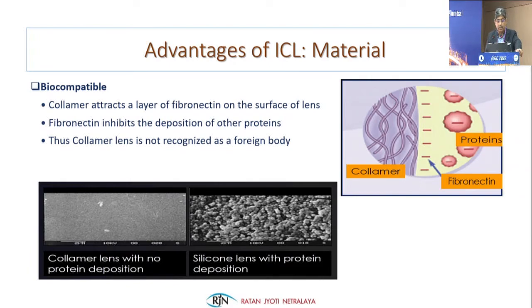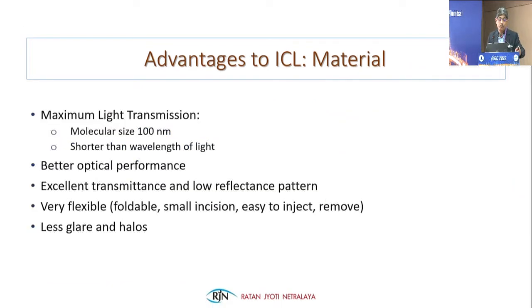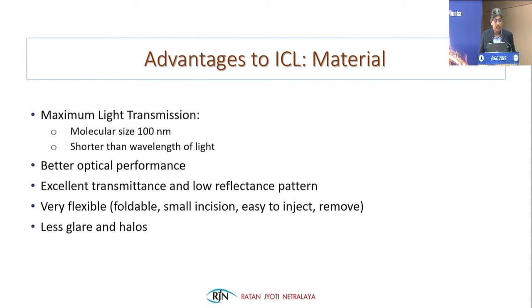The collamer material on the left versus silicone on the right — you can make out the clarity of the collamer material. The polymer molecular size is 100 nanometers shorter than the wavelength of light, giving maximum light transmission and better optical performance, excellent transmittance, low refractive index, and very flexible — foldable through a small incision, easy to inject and easy to remove. There are fewer glare and halo issues with these lenses.